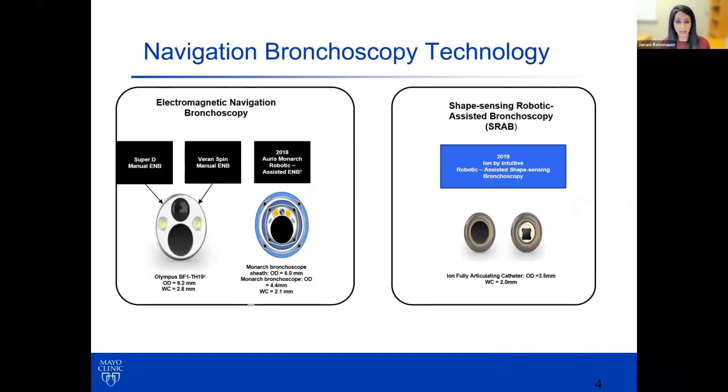The two systems are inherently different in terms of the way they function. Many of you might be familiar with electromagnetic navigation as used in superdimension or the Veran Spin system. The Auris Monarch system uses electromagnetic navigation in a similar fashion. The outer diameter of the catheter is six millimeters in size, with a working channel of 2.1 millimeters. The Intuitive system utilizes a technology called shape sensing robotic bronchoscopy, with an outer diameter of 3.5 millimeters and a working channel of 2 millimeters.